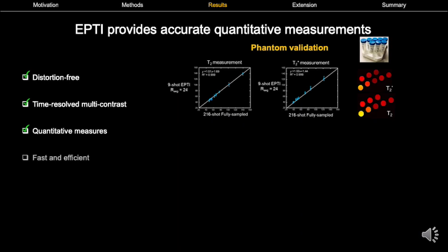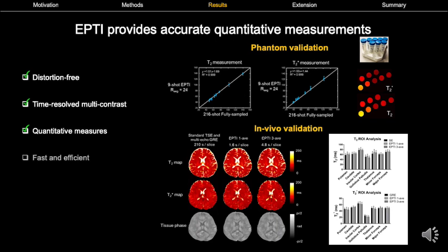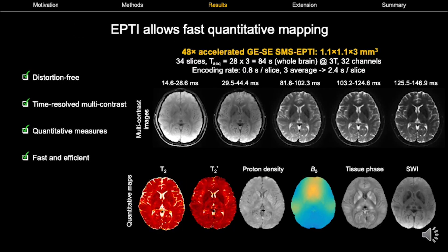Using EPTI's signal evolution information, we can obtain quantitative measurements such as T2 and T2 star. We performed both phantom and in-vivo experiments and successfully validated its ability to get accurate T2 and T2 star measurements in much shorter acquisition time. EPTI allows rapid quantitative mapping using a 48-fold accelerated gradient and spin echo SMS EPTI at 1.1 x 1.1 x 3 mm for whole brain coverage. One average of EPTI takes only 28 seconds with an encoding rate of 0.8 seconds per slice. Acquiring three averages to boost SNR results in a total acquisition of 84 seconds for all multi-contrast and quantitative maps.